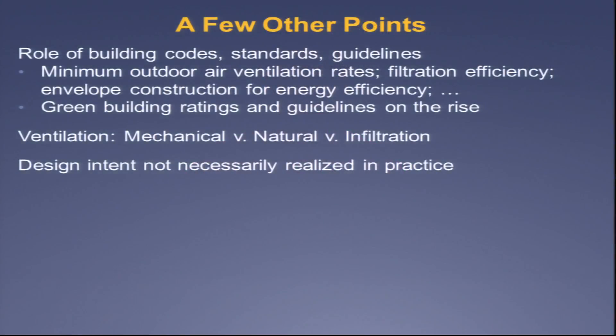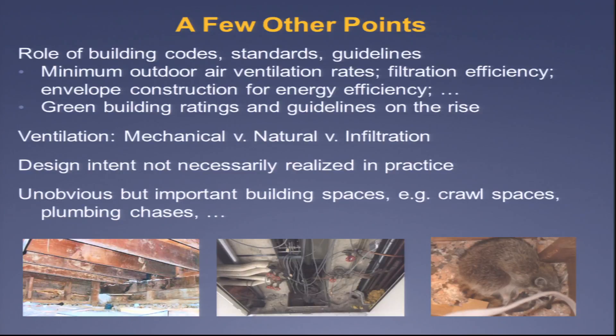Yesterday and at the meeting in April, we talked about the EPA-based study — 100 randomly selected buildings studied in the mid-90s. I looked at the ventilation data, and about half of the ventilation measurements were below the design value. Even more interesting: in half of the buildings, nobody could find a record of the design ventilation rate. My last point is that there are important spaces in buildings that are sometimes unoccupied and unobvious. The one on the left is a crawl space. When we characterize a building, are we measuring what's going on in the crawl space or even thinking about it? The one in the middle is a plumbing chase across the hall from my office — four stories tall, dirty, pipes that may leak.